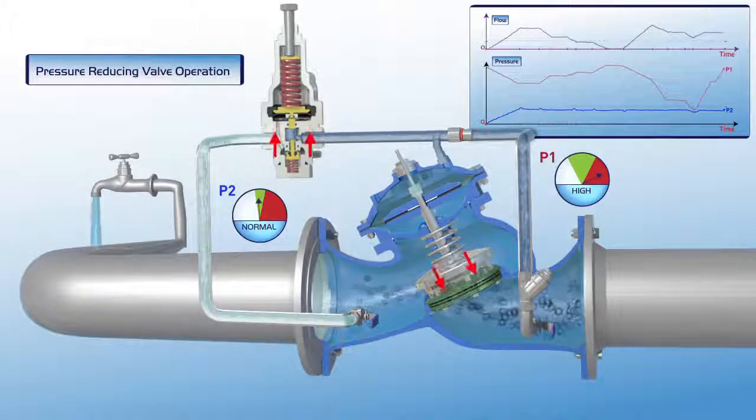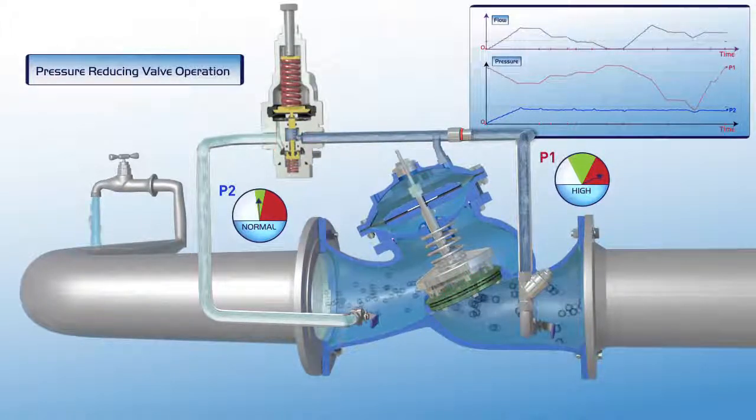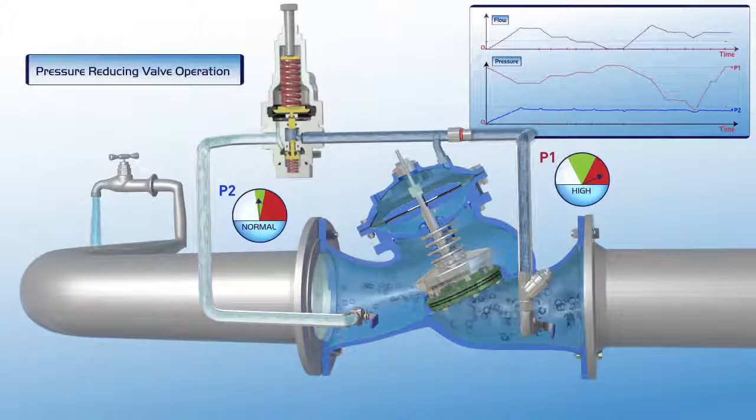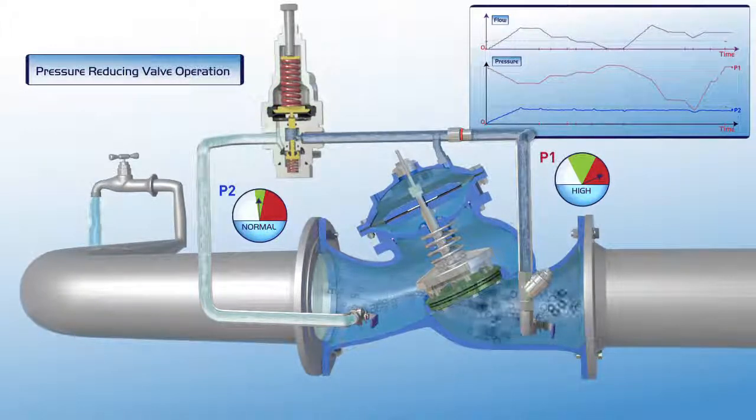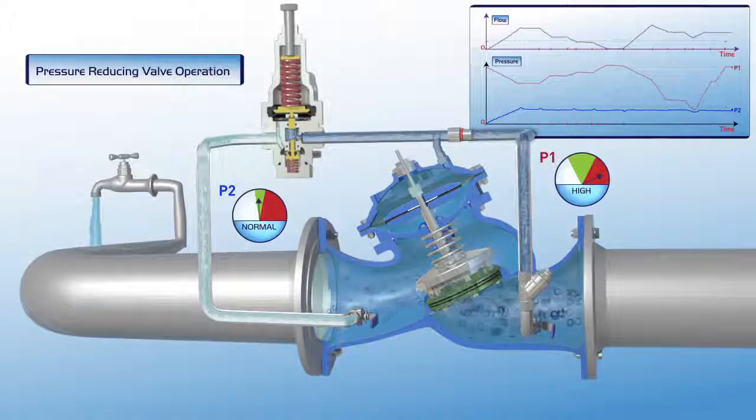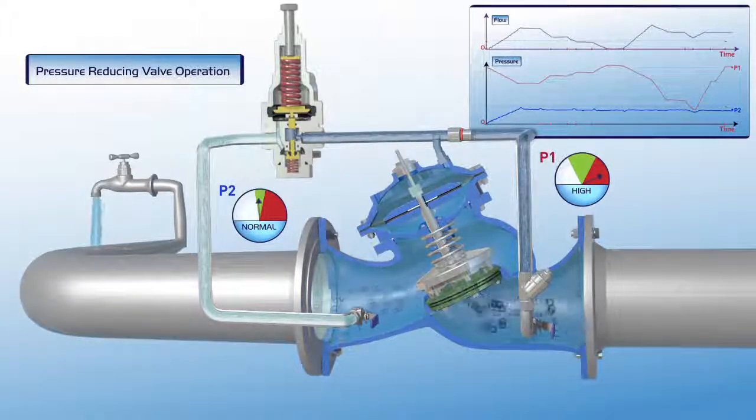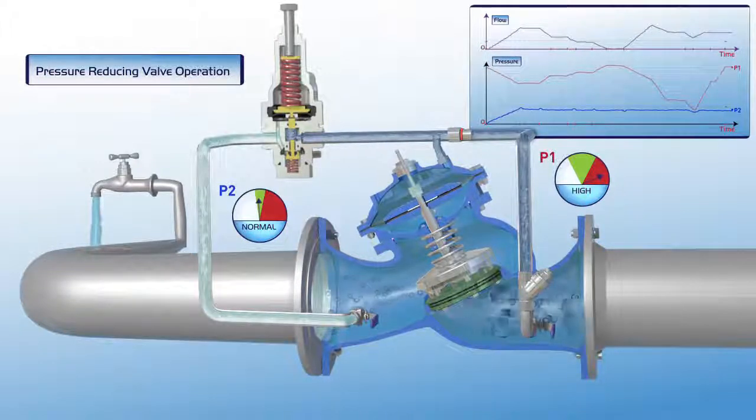As shown on the chart, the valve maintains a constant downstream pressure, even when the upstream pressure rises to a very high level. As illustrated in this film, the BERMAD pressure-reducing control valve reduces higher upstream pressure to lower constant downstream pressure, regardless of fluctuating demand or variations in upstream pressure.